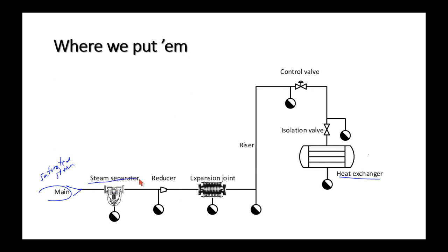We might have a steam separator, and you have seen those in the Synovus building in the main floor lab. What do we find at the base of the steam separator? A steam trap discharging condensate back into the condensate return system. So maybe we've got 90% dry and saturated going in, and maybe what leaves the steam separator might be, say, 98% dry and saturated.